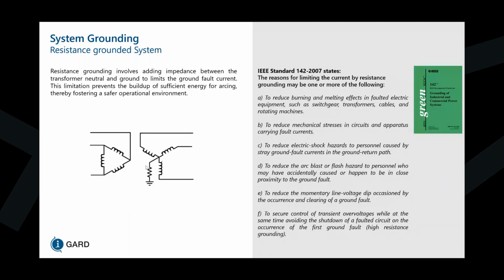We also help to reduce the momentary line-voltage dip occasioned by the occurrence and clearing of a ground fault in comparison to what we see in other systems, and we secure control of transient overvoltages while at the same time avoiding the shutdown of a faulted circuit on the occurrence of the first ground fault. So mostly the main benefit is reducing the electrical and mechanical stresses that we would see in a solidly grounded system when we have high levels of fault current by reducing that fault current to a specific value that we dictate, typically 5 or 10 amps for low voltage systems.